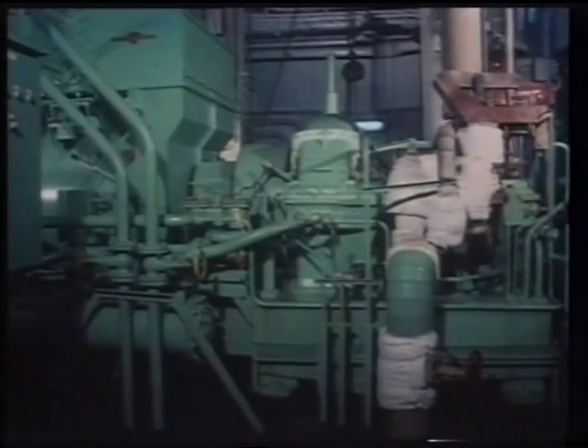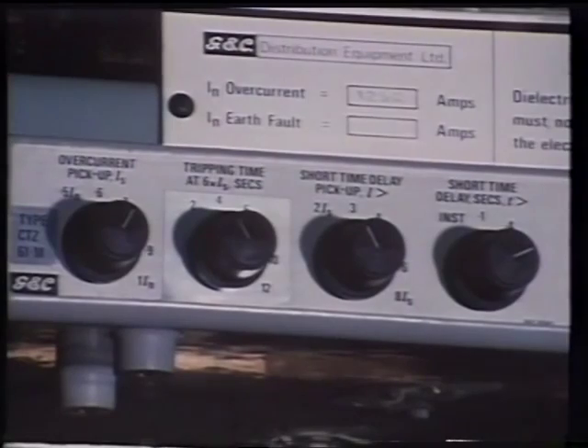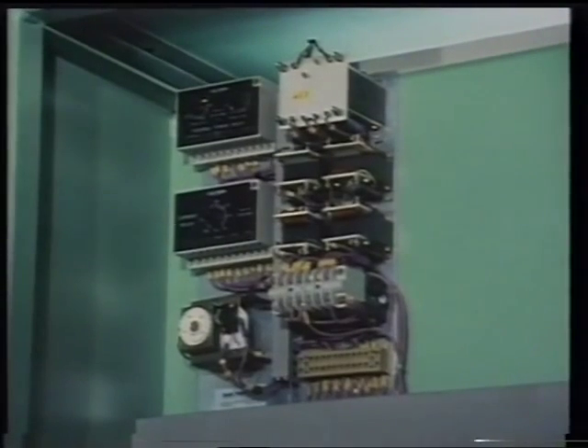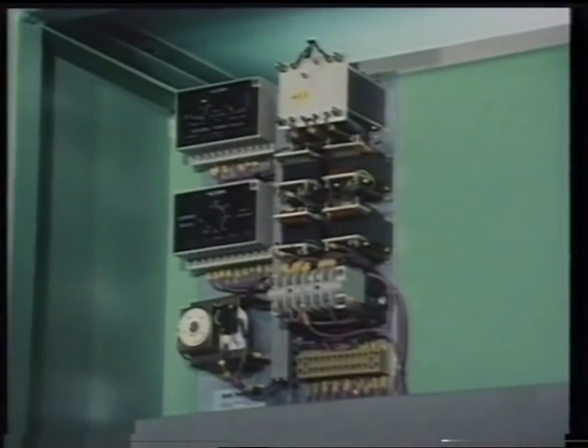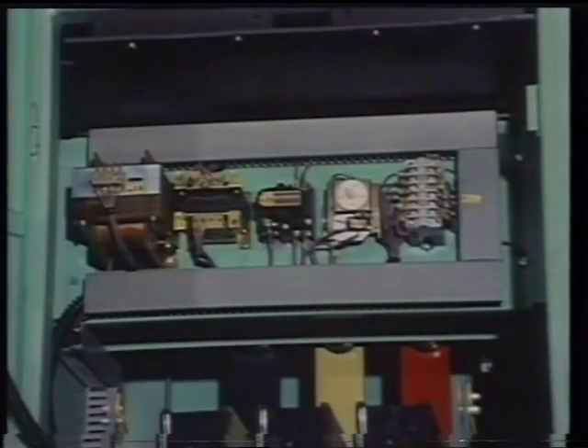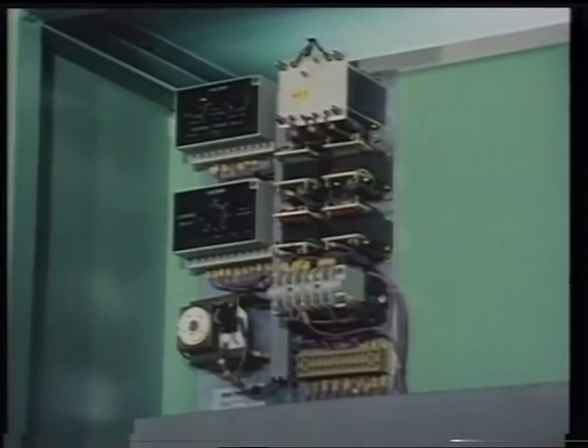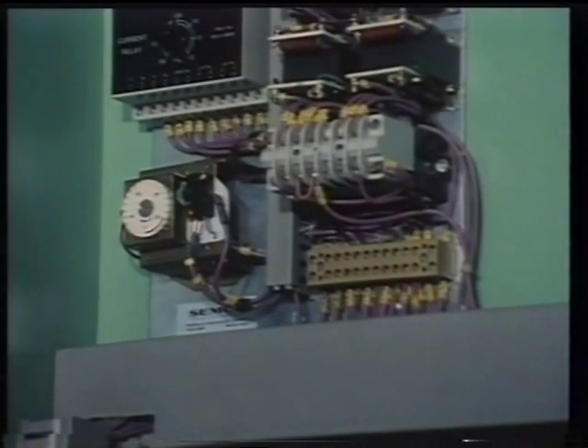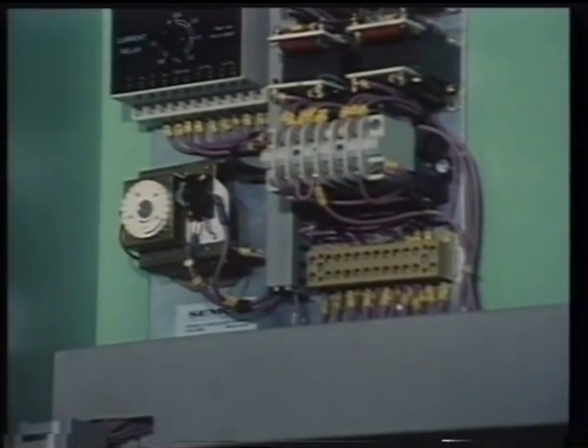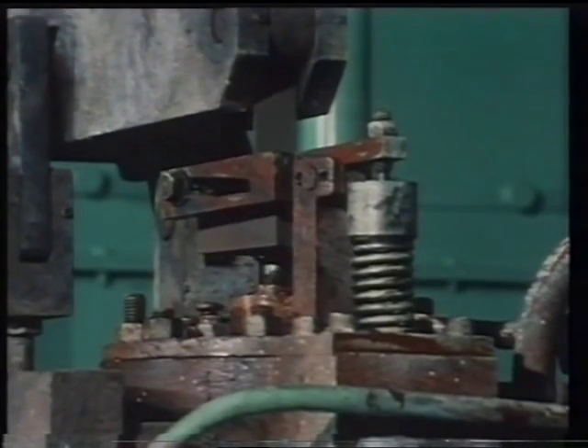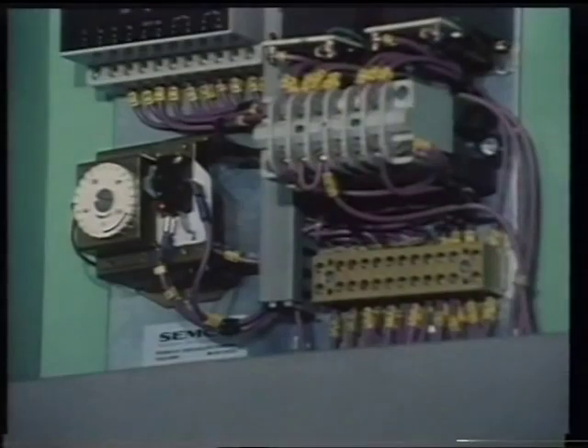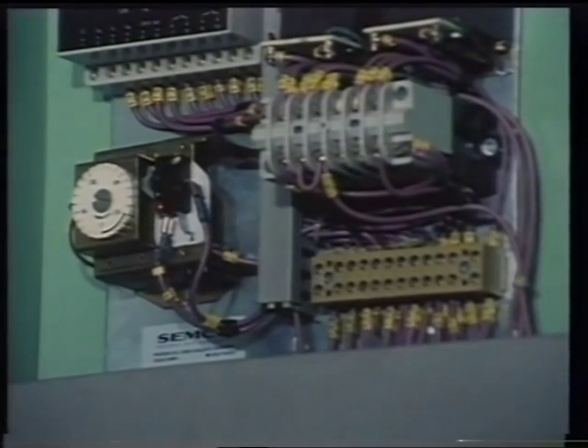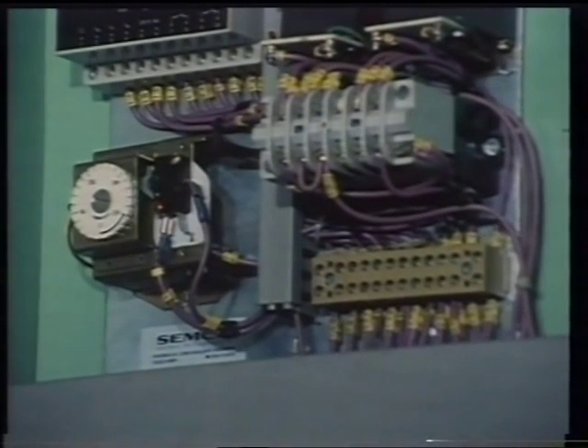An alternator is protected by a number of devices, such as overcurrent, short circuit and under-voltage trips in the circuit breaker. Additional protection is provided by the reverse power relays and preferential trip relays. Their function is to monitor the power supply between an alternator and the bus bars. If the power flow is reversed from the bus bars into the alternator, the reverse power relay disconnects the alternator from the bus bars.